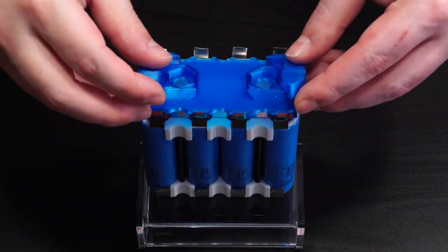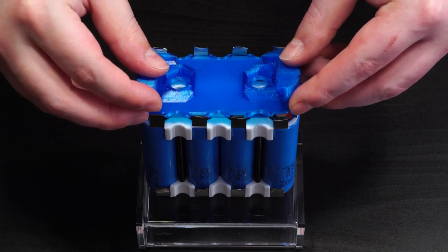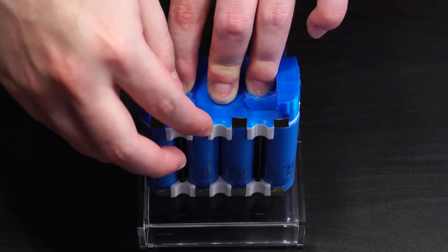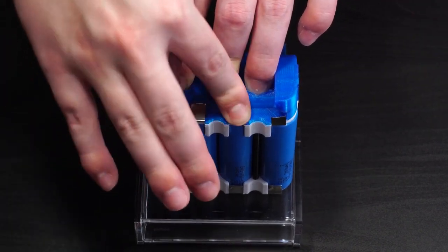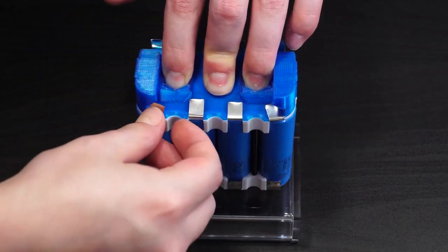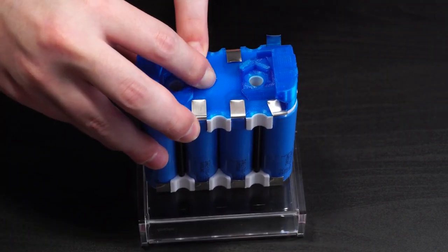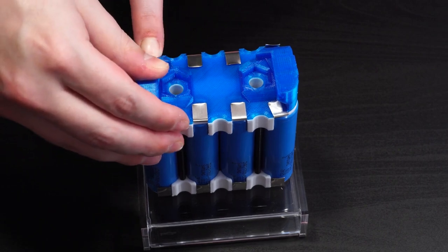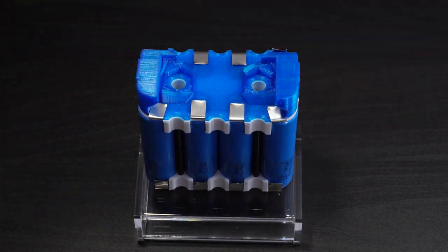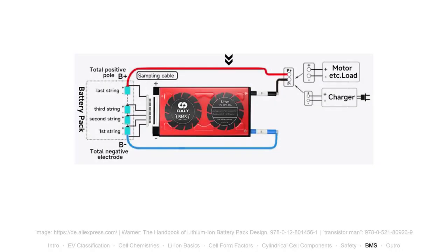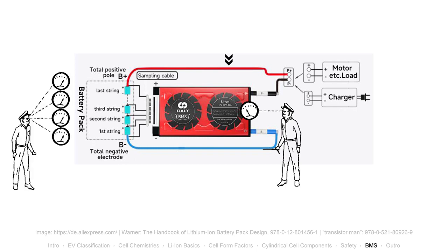Another purpose of the BMS is ensuring longevity. Especially in automotive applications, a lifetime of up to 15 years is expected. A BMS can enforce temperature-dependent operational limits, which is a major factor determining the lifetime of batteries. To enforce the current envelope, the BMS must monitor the complete battery current. This is often done on the negative pole of the battery. The BMS must also monitor the voltage of every single cell.